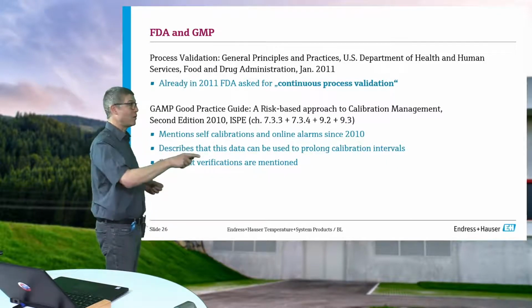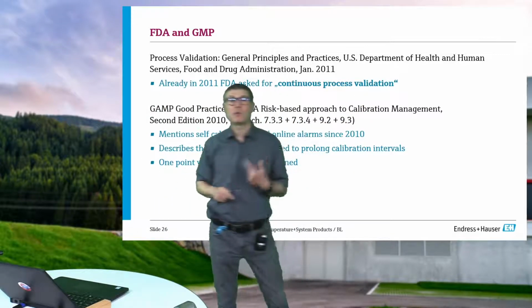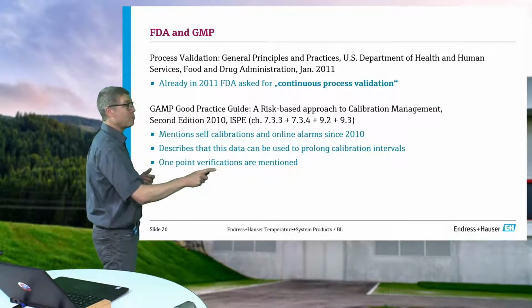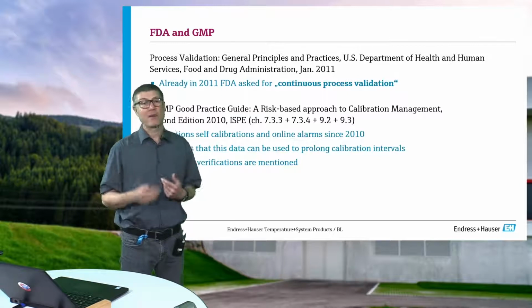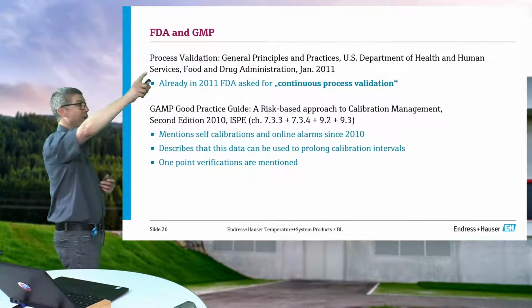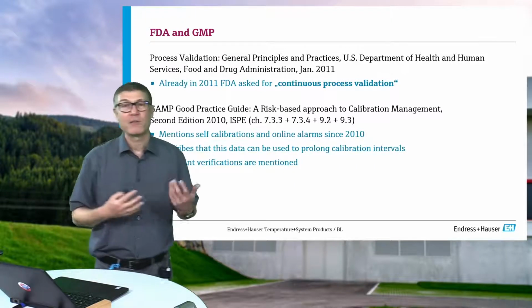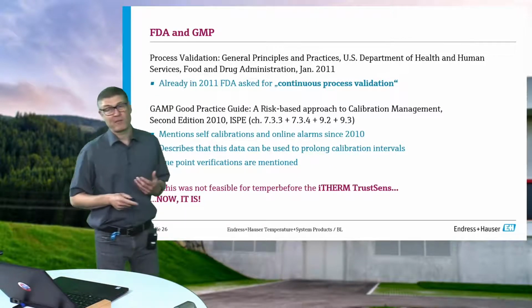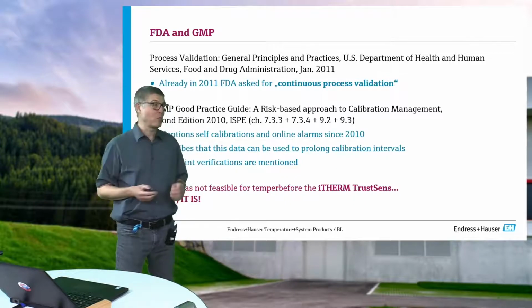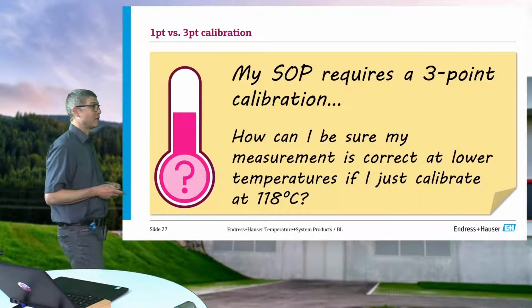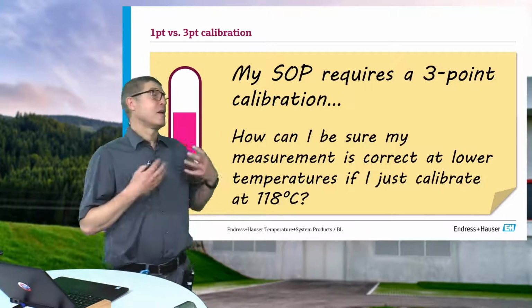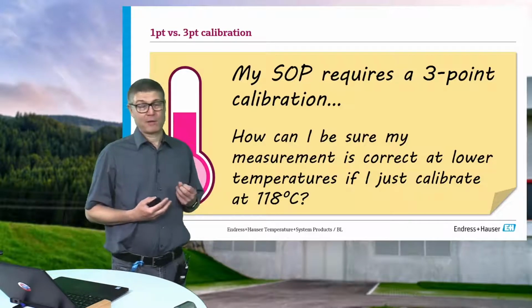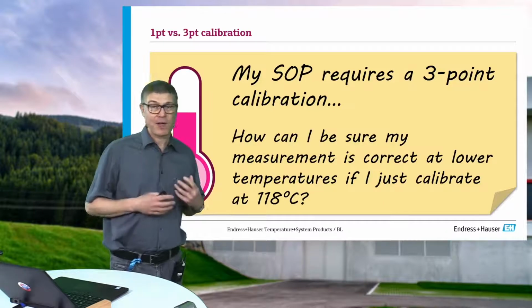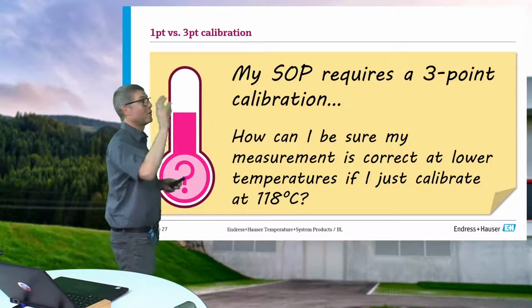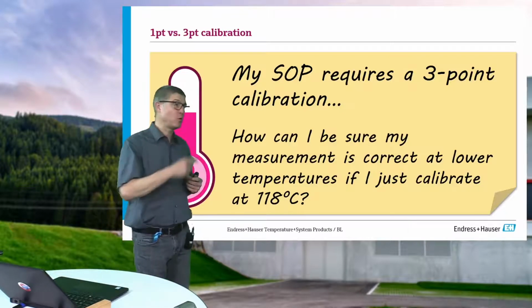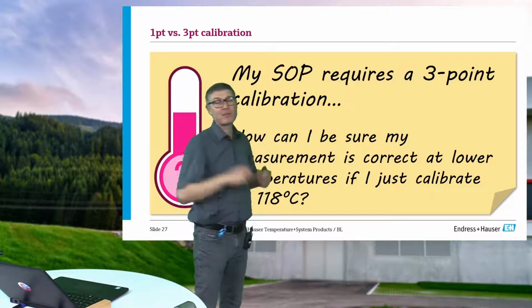So what we have done is we have not continuous process validation, we have continuous process calibration, and we have 1-point calibration. So we already exceed the needs of the GMP and FDA rules, which are written down in 2011 and 10, where for sure nobody believes in a self-calibrating thermometer. Now it's available. So we already cover the rules of the GMP, and as your question says, your SOP requires a 3-point calibration. We can do an academic discussion about it, and we will start with it now. So you can do it. You should do it. But what you can do is use this everyday calibration results to make your intervals longer.